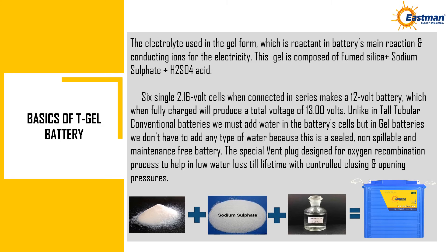The gel electrolyte is composed of fumed silica, sodium sulfate, and sulfuric acid. Six single 2.16 volt cells connected in series make a 12 volt battery, which when fully charged produces 13.00 volts. Unlike conventional tubular batteries where water must be added to the cells, gel batteries do not require any water addition because they are sealed, non-spillable, and maintenance-free. A special vent plug is designed for oxygen recombination to help minimize water loss over the battery's lifetime, with controlled closing and opening pressures.